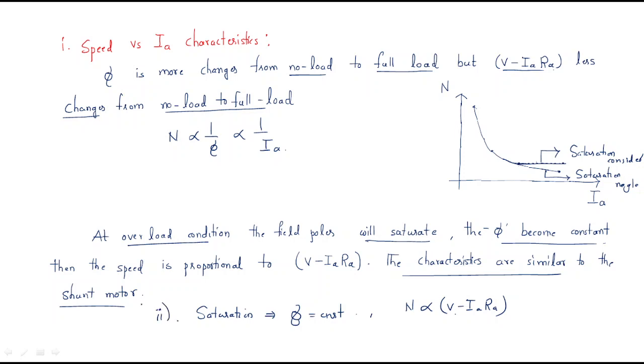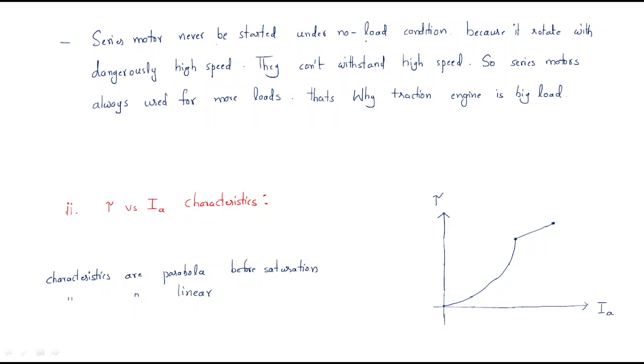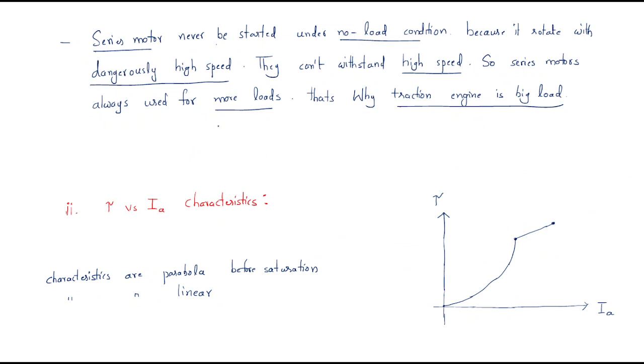Saturation is a rare case since we do not normally operate in overload. Most importantly, DC series motors must never be started under no-load condition, because they rotate at dangerously high speed under no load and cannot withstand it. The series motor should always be used with more load — traction engines are a big load, which is why the DC series motor has major applications in traction.